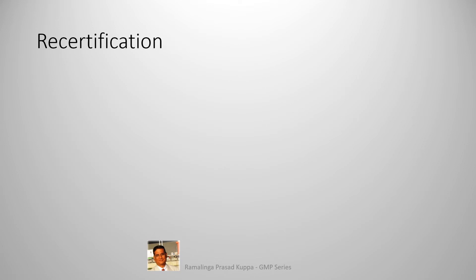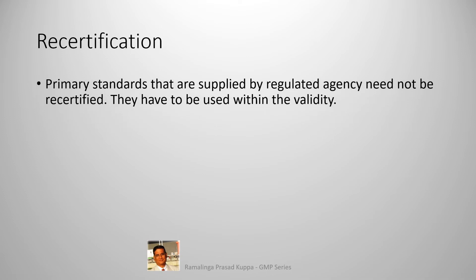Primary standards that are supplied by a regulatory agency need not be recertified. They have to be used within their validity period. The compendial standards should be used within the validity period and are not recertified by the receiving lab. Whenever a new lot is made available, the older version should be discarded.